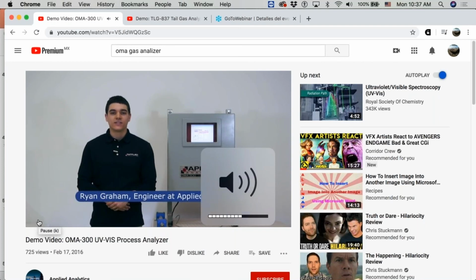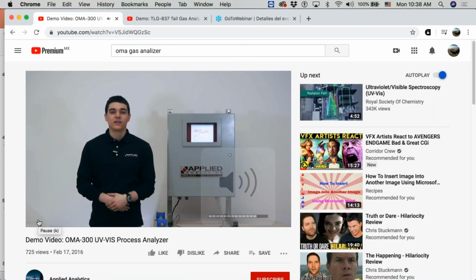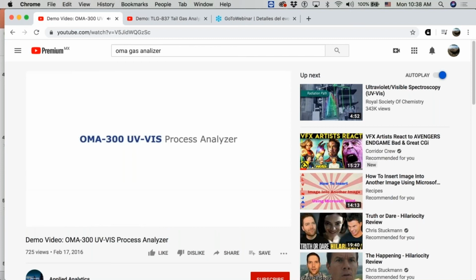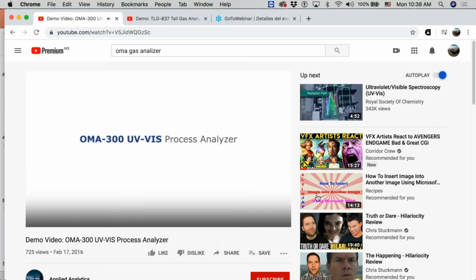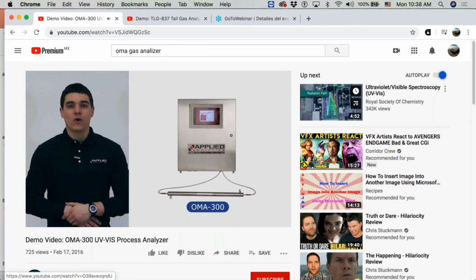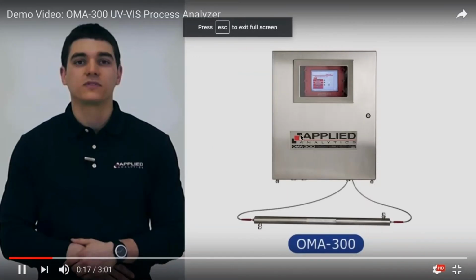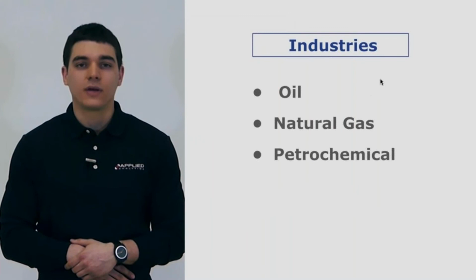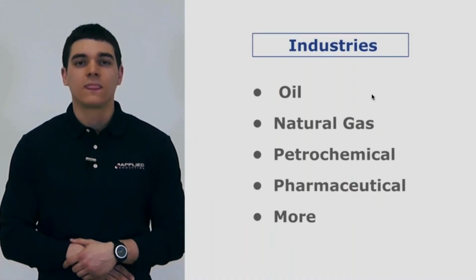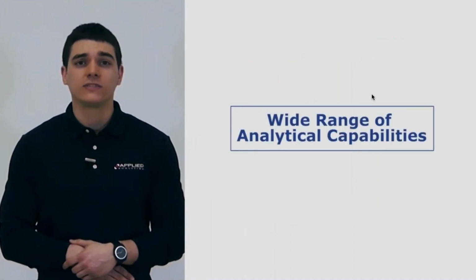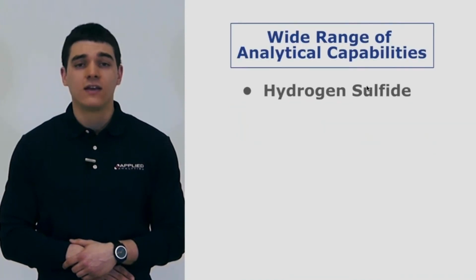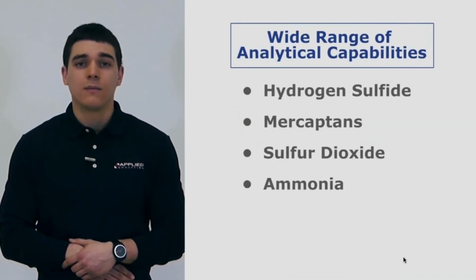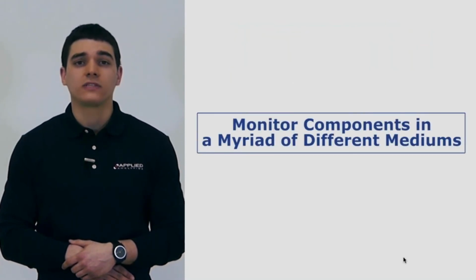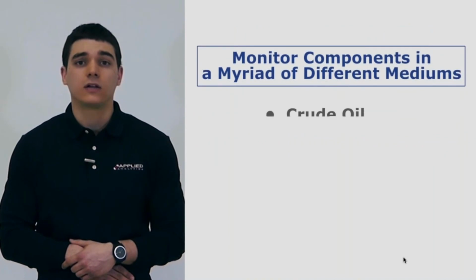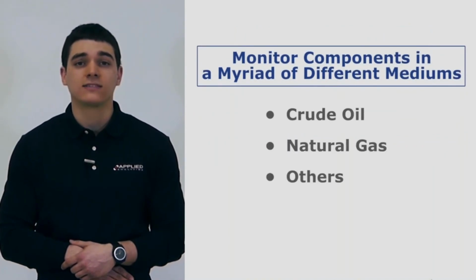I'm one of the field service engineers here with Applied Analytics. We'd like to take just a little bit of your time to demonstrate the OMA 300 UV-Vis process analyzer. The OMA 300 offers a uniquely robust approach to solving some of the most common analytical demands in the oil, natural gas, petrochemical, and pharmaceutical industries. The OMA 300 has a wide range of analytical capabilities, including hydrogen sulfide, mercaptan, sulfur dioxide, ammonia, and chlorine, just to name a few. Moreover, our process analyzers can monitor these components in a myriad of different mediums, including but not limited to crude oil and natural gas.